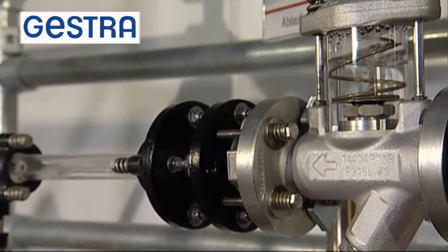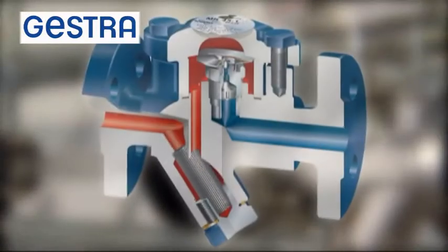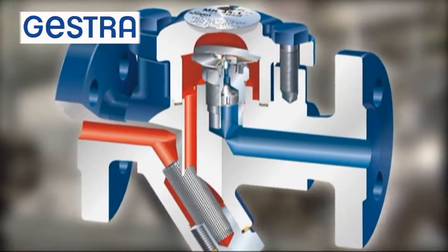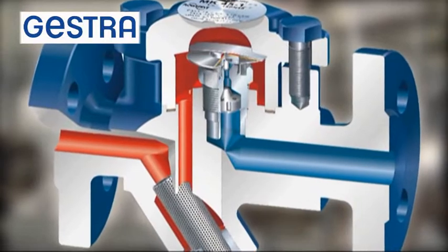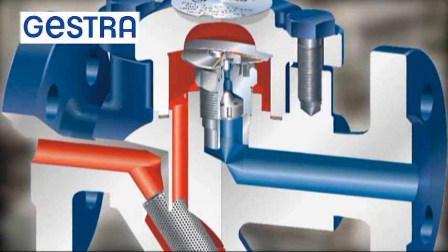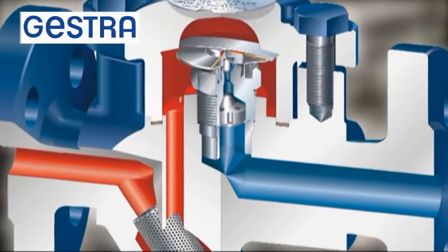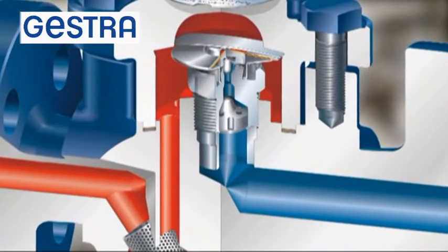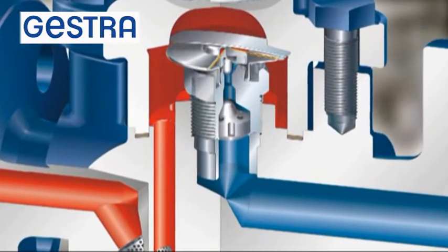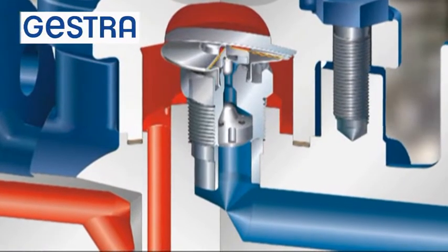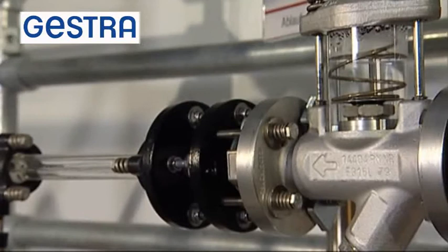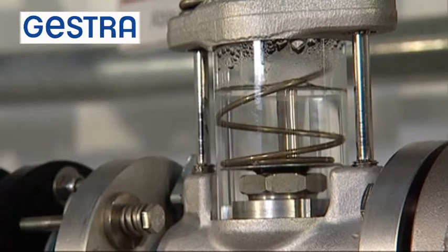If the condensate flow rate is less than 100 kilograms per hour, the GESTRA tandem seat should be used. For this variant, a self-centering valve cone is integrated into the seat assembly. The valve cone has a certain freedom of movement and is able to close off the main seat before the second seat reaches the flat gasket. This provides a further guarantee of tightness, even in the presence of dirt particles. Moreover, the pressure drop over two stages reduces wear and extends the life of the trap.